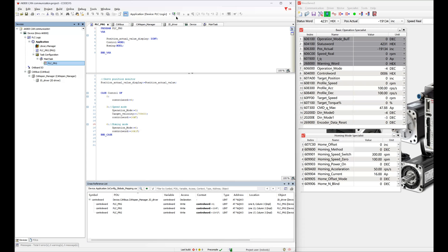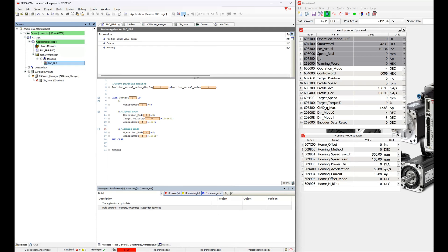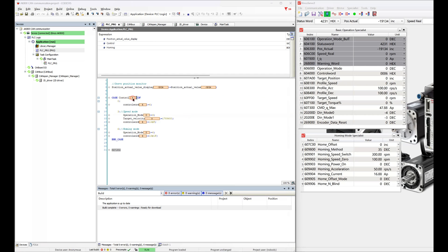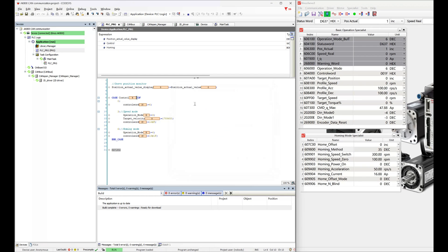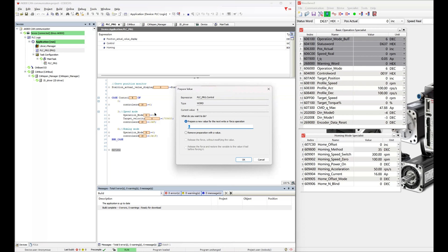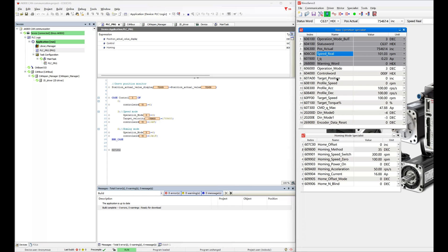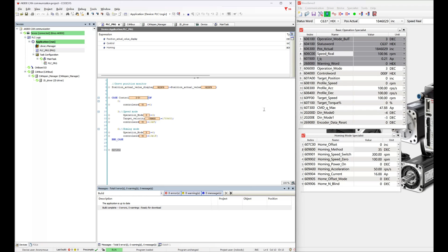Then log into the PLC and start running. We can see that the PLC is online. The SDO initial setting of the return mode has been written into the servo, and the actual position change of the servo can be real-time monitored. Changing the program's control variable to 6, you can see that the current position of the servo has been cleared. Change the control mode to 3 and you can see that the servo will run at 100 RPM. After changing to 0, the servo will stop running.